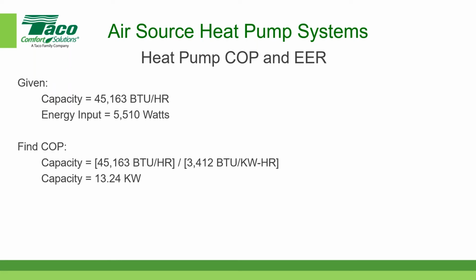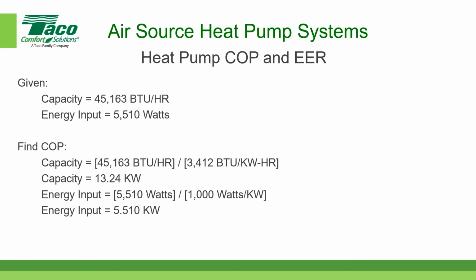Well, what about the input? Well, the input is 5,510 watts. If you divide that by 1,000 watts per kW, that comes out to 5.51 kW. Now if you divide the 13.24 by 5.51, that's the capacity divided by the input, we have a COP equal to 2.40. Now wasn't that simple? Piece of cake. Anybody have any questions about that? This is the fundamental math that we use when we calculate the capacity and the efficiency of a heat pump.